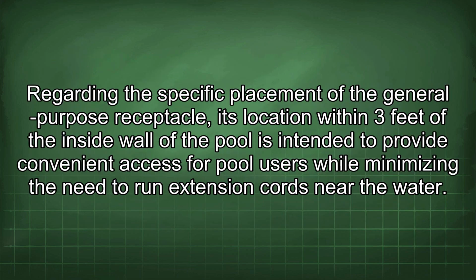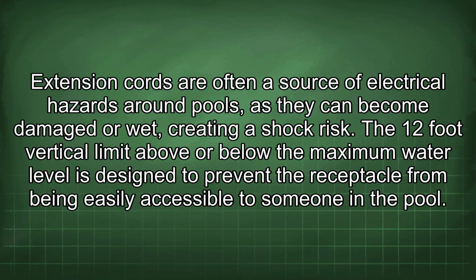Regarding the specific placement of the general-purpose receptacle, its location within 3 feet of the inside wall of the pool is intended to provide convenient access for pool users while minimizing the need to run extension cords near the water. Extension cords are often a source of electrical hazards around pools, as they can become damaged or wet, creating a shock risk. A 12-foot vertical limit above or below the maximum water level is designed to prevent the receptacle from being easily accessible to someone in the pool.